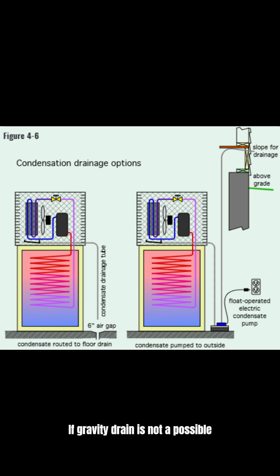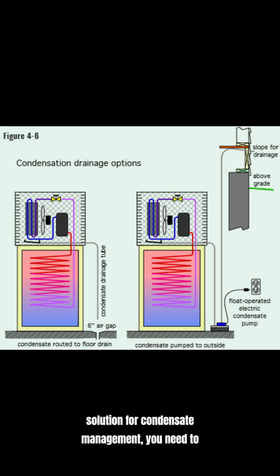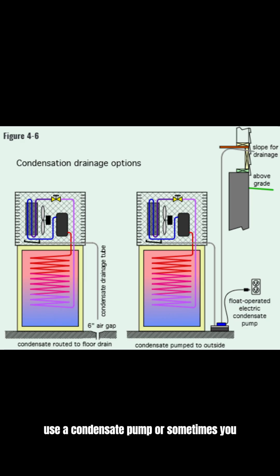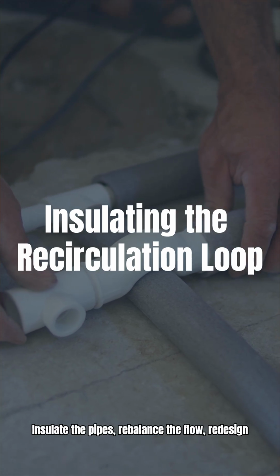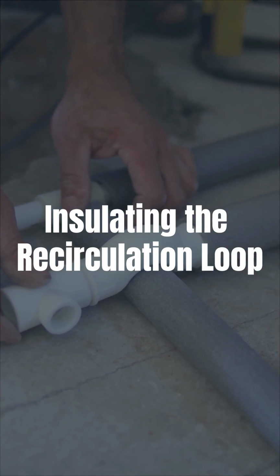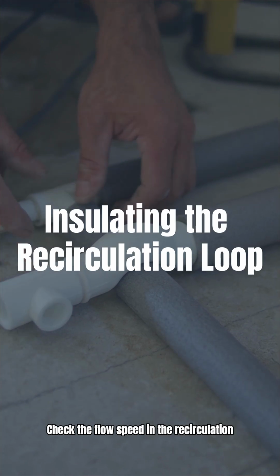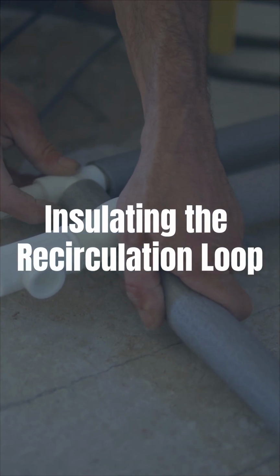If gravity drain is not a possible solution for condensate management, you need to use a condensate pump, or sometimes you can tie into an existing AC drain if you have one. Insulate the pipes, rebalance the flow, redesign the loop. Check the flow speed in the recirculation loop. We want it under 5 feet per second.